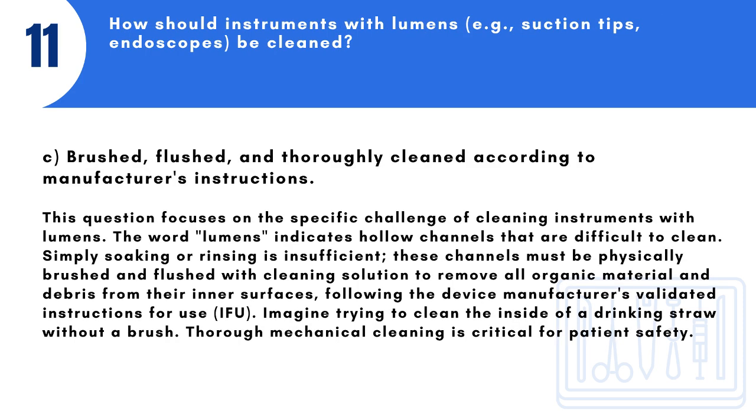Answer: C. Brushed, flushed, and thoroughly cleaned according to manufacturer's instructions. This question focuses on the specific challenge of cleaning instruments with lumens. The word lumens indicates hollow channels that are difficult to clean. Simply soaking or rinsing is insufficient. These channels must be physically brushed and flushed with cleaning solution to remove all organic material and debris from their inner surfaces, following the device manufacturer's validated instructions for use, IFU. Imagine trying to clean the inside of a drinking straw without a brush. Thorough mechanical cleaning is critical for patient safety.